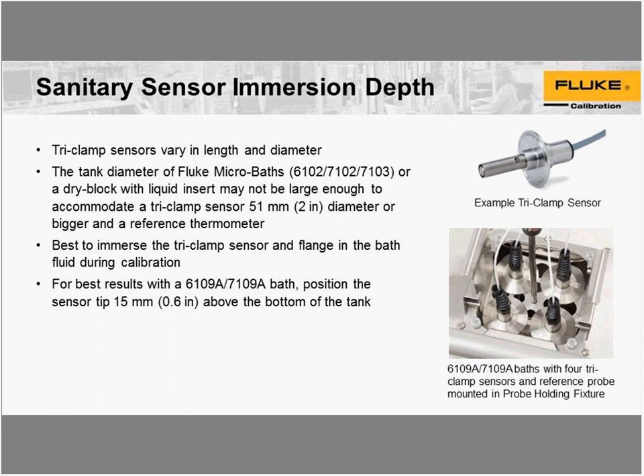The tri-clamp bath, as we are referring to it, is designed to accommodate 4 2-inch diameter flanged sensors. The tri-clamp sensors do have a variety of diameters. I think they go up to 3-inch diameter. So the tank will hold 4 2-inch diameter flanged sensors, and so when you immerse them, we recommend that you immerse the sensor and also the flange, because it's just such a large piece of mass that can conduct heat where the sensor is at. There's flexibility here. If for some reason you have a calibration application where you don't need to measure the sensor immersed to the flange, then of course you don't have to. But the key is that it does accommodate that.